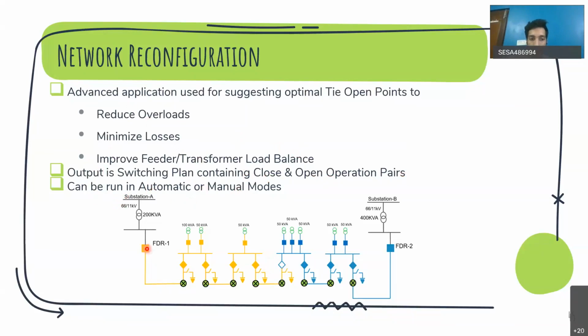Okay. Again, in this example, you have feeder 1 in orange color, feeder 2 in blue color. There is a tie open point in between here. Okay. So the output of this network reconfiguration will always be to shift this open point this side or this side. Why or how it should shift is, for example, in this case, say this power transformer is of 200 kVA. Okay. So feeder 1 is feeding 3 distribution transformers of total 200 kVA. So in this hypothetical scenario, it is at 100% loading.